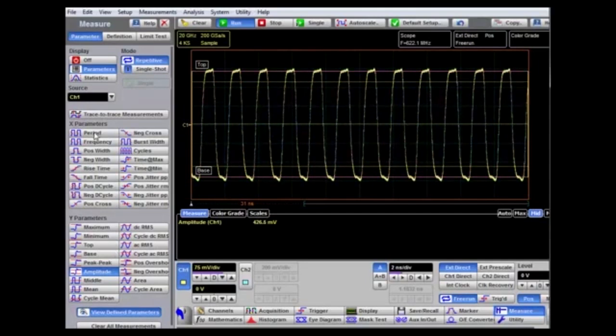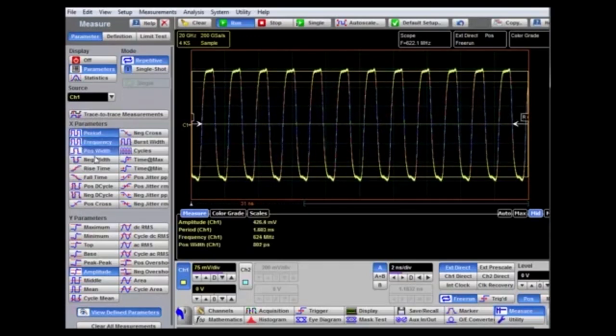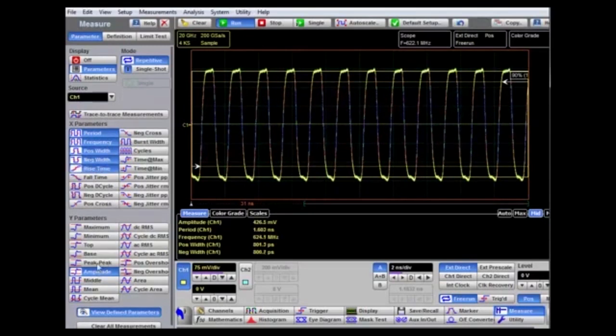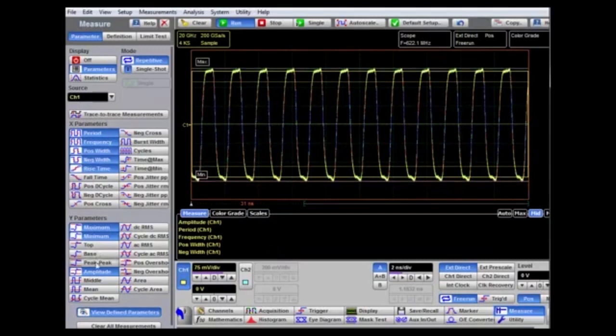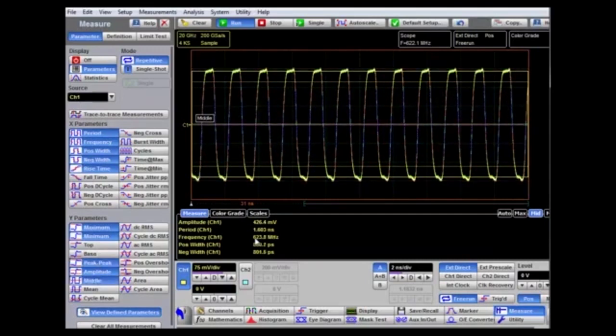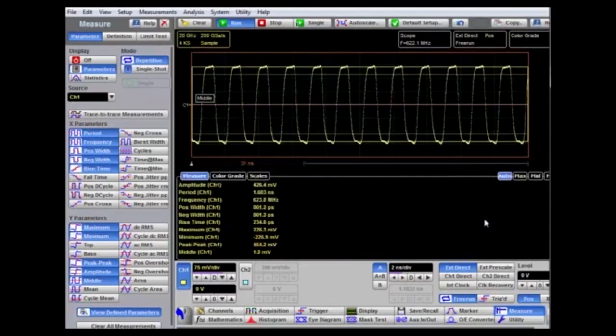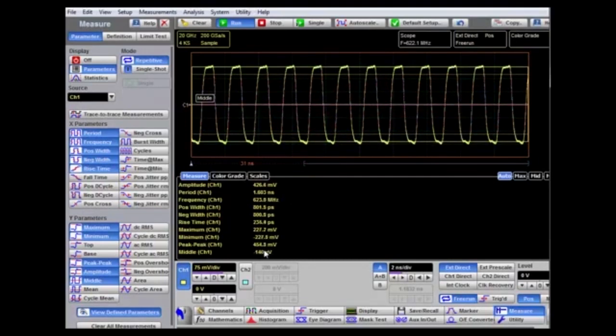We can turn on up to 10 measurements at once — for example, 5 time measurements and 5 amplitude measurements. All 10 can be seen in the measurements box. Selecting the auto option will automatically scale the measurements box to display all 10 measurements being updated in real time.